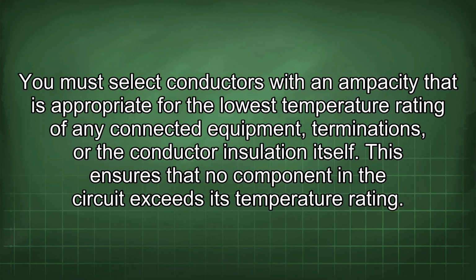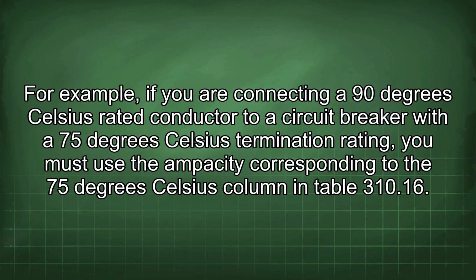You must select conductors with an ampacity that is appropriate for the lowest temperature rating of any connected equipment, terminations, or the conductor insulation itself. This ensures that no component in the circuit exceeds its temperature rating. For example, if you are connecting a 90 degrees Celsius rated conductor to a circuit breaker with a 75 degrees Celsius termination rating, you must use the ampacity corresponding to the 75 degrees Celsius column in table 310.16.